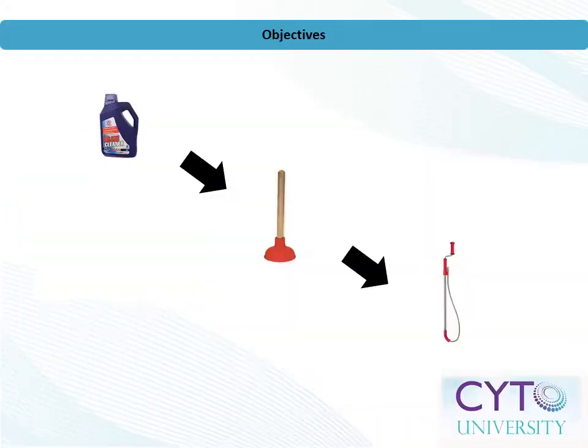In this presentation, I will discuss common troubleshooting techniques used to identify and eliminate clogs in a flow cytometer, starting with the simplest and least invasive methods, and moving towards more complex and more interventional methods. May we never forget Shapiro's first law of cytometry: a 51 micron particle clogs a 50 micron orifice.